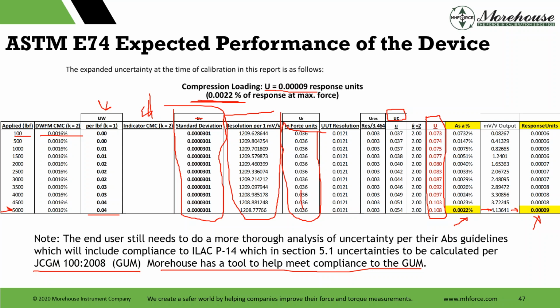Though again, when we say compression loading, this is exactly what we're doing. We're taking the sum of the squares of all the individuals for that formula, and we're coming up with a percentage of max response. So really, this device was calibrated by our dead weights, good to 0.0016, and at the end, we're saying, hey, this device at capacity, this load cell, 0.002. But if we go look down at 100, it's 0.07. At 500, it's 0.0147.